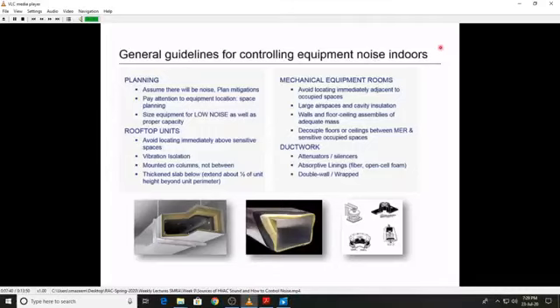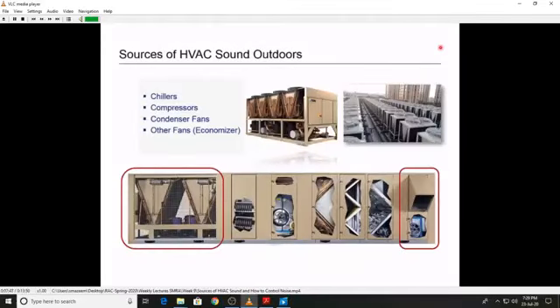Let's move on finally and take a couple seconds to look at HVAC equipment outdoors. Again, looking at sources of sound. When you're concerned with the sound outdoors, you've got chillers and compressors, condenser fans, and then other fans related to your units if you've got an air handling system that's outdoors, because some of those fans have exposure to the outdoors. Although, in general, as a very rough rule of thumb, for an air handling unit, the compressors and condenser fans would be louder than noise coming from fans handling indoor air.